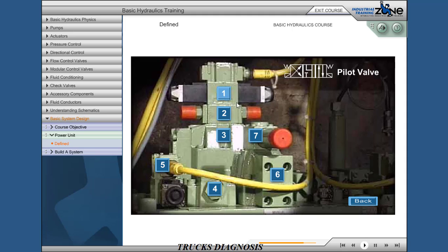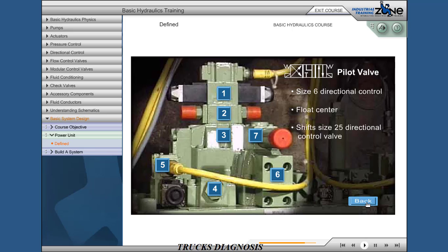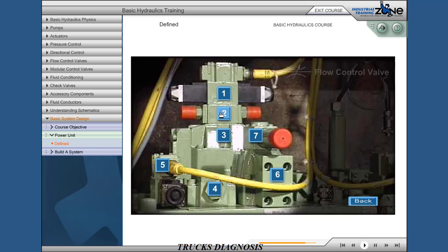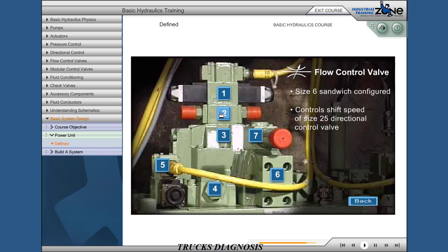Pilot valve: size 6 directional control valve, float center. Shifts the size 25 directional control valve. Flow control valve, size 6 sandwiched configured, controls shift speed of the size 25 directional control valve.